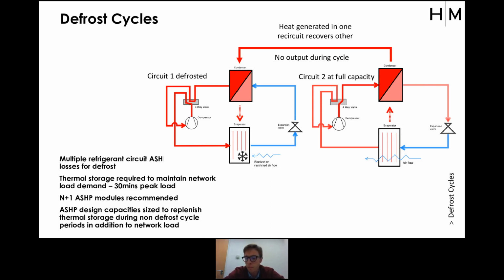So we would recommend thermal storage to improve your operation of the heat pumps. You don't have this constant turning off and on, but it's also sized to benefit your defrost cycles and overcome issues with that, so that you can meet whatever demands, so peak demands on the network, whilst some of your units are in defrost operation for whatever period. And we use a rule of thumb of about 30 minutes peak load for thermal storage for your energy center. But we also, as a belt and braces at this stage, until we probably get more science to it, but the manufacturers are quite good now in giving advice, look at an N+1 resilience, maybe for your early design stages, to account in your plant sizing and space take.